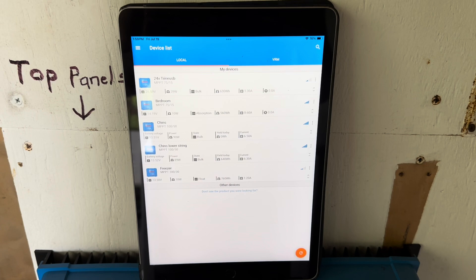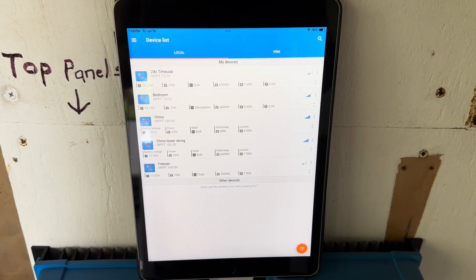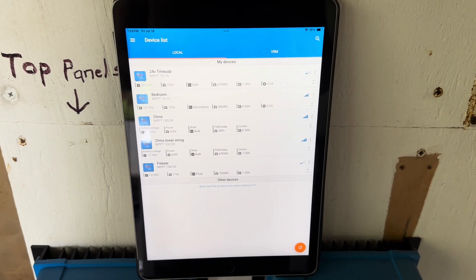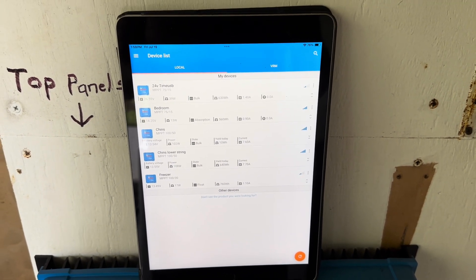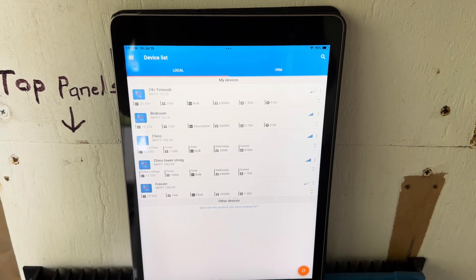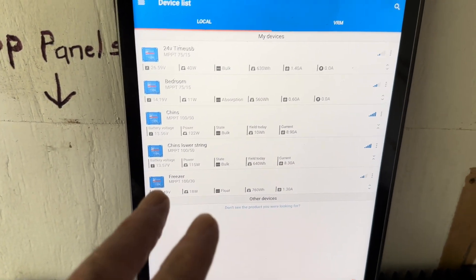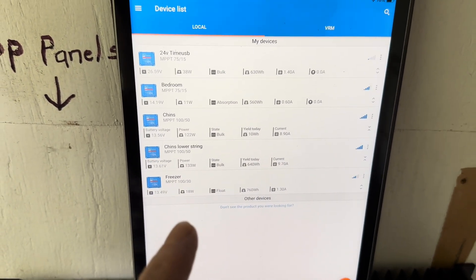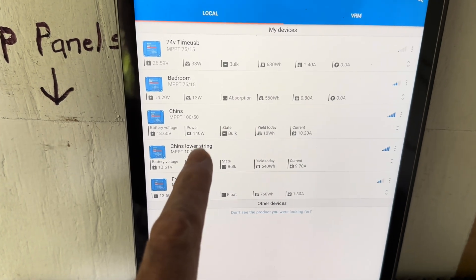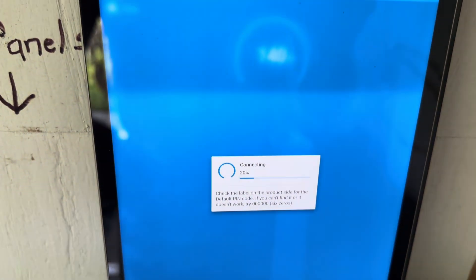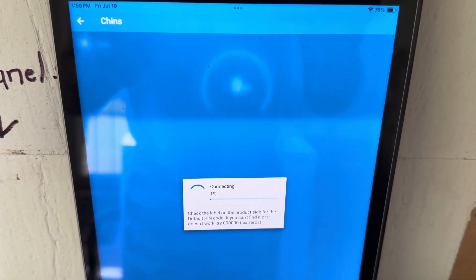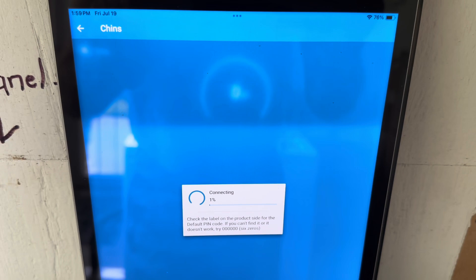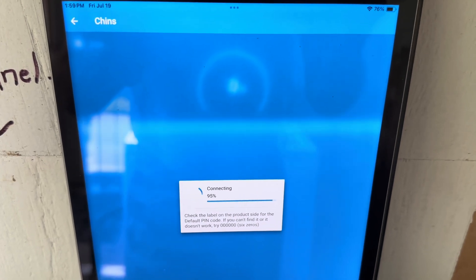The first thing that I did is I of course ran out there and looked at the panels, the panel array real quick. Everything looked good - I was thinking geez, did a tree fall down or something out there? But anyway, just on quick visual inspection it looked good, but yeah, this top string was registering absolutely zero watts. And there it goes again - what in the world?